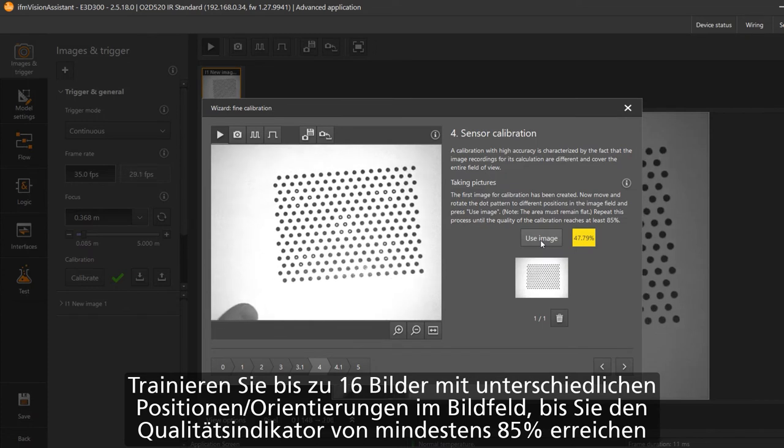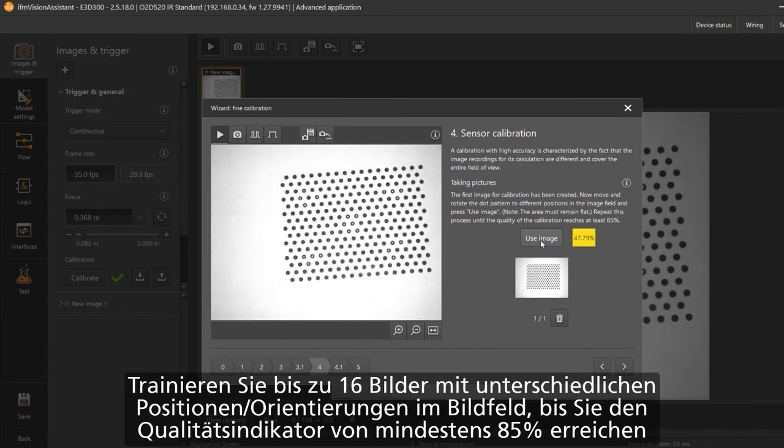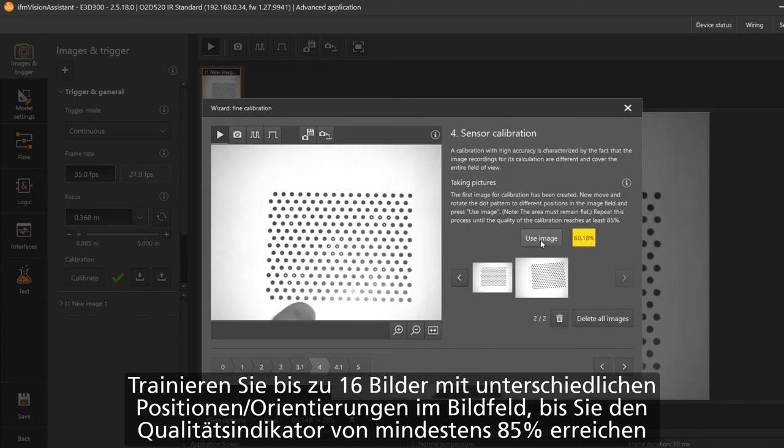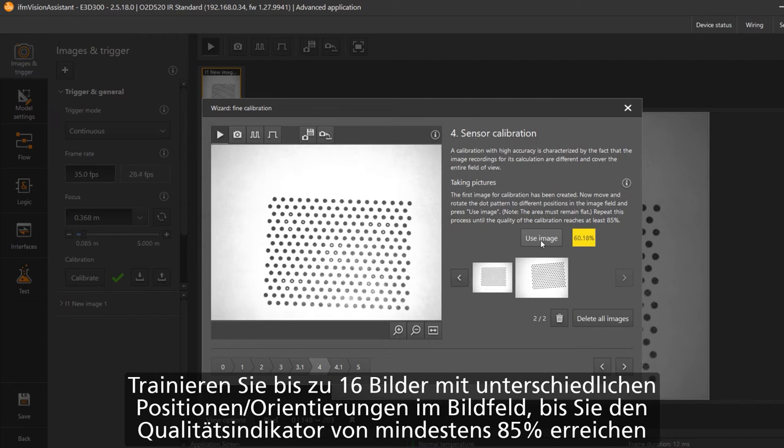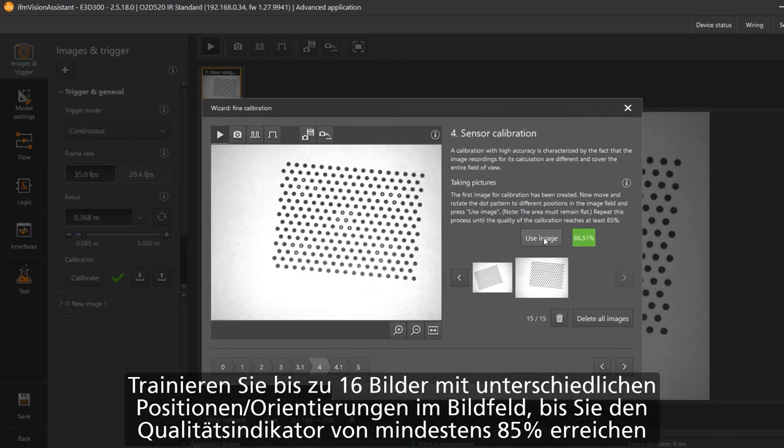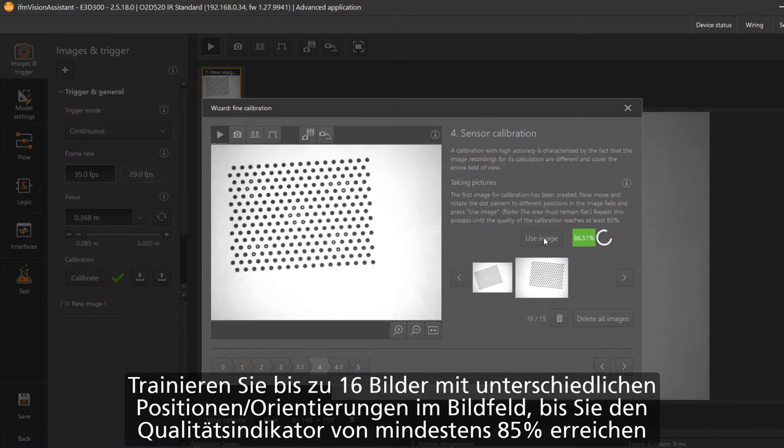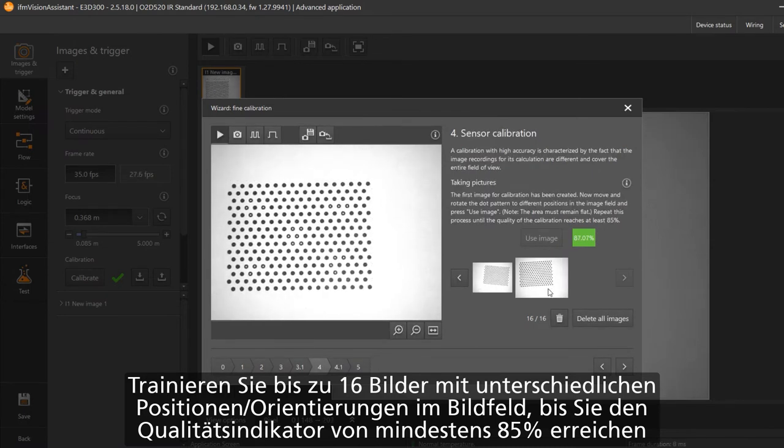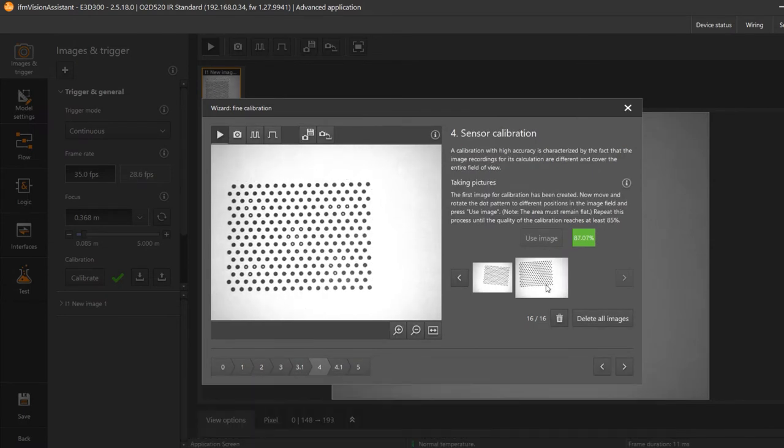Place your image in the middle and press the use image button. Change the orientation in both directions and press use image again. The pattern needs to be complete in the field of view. Repeat this process until the shown percentage shows a value higher than 85%.